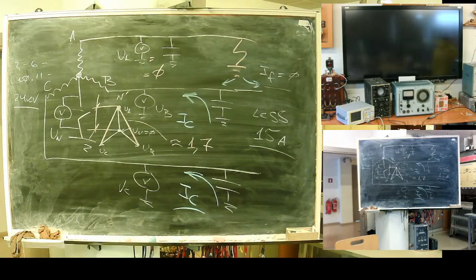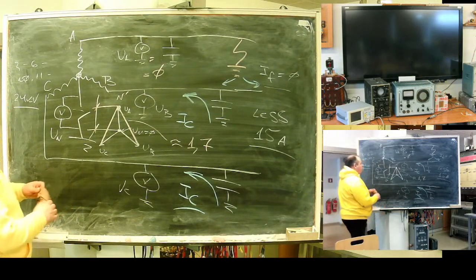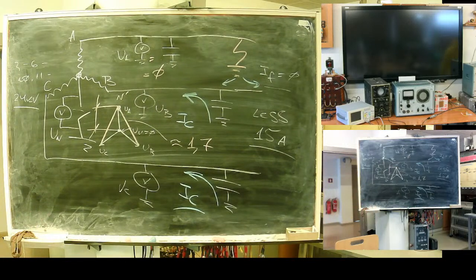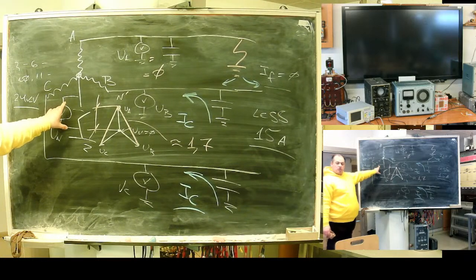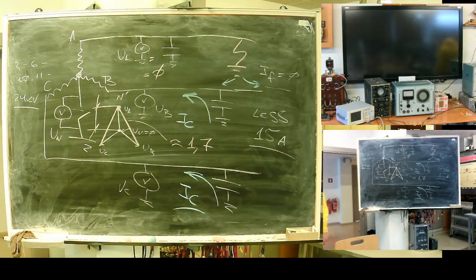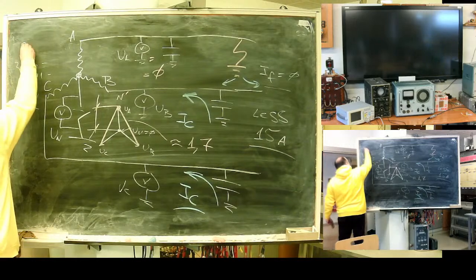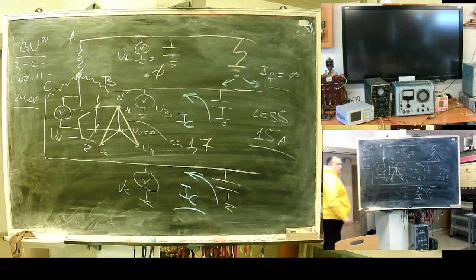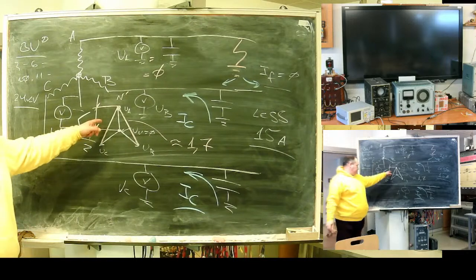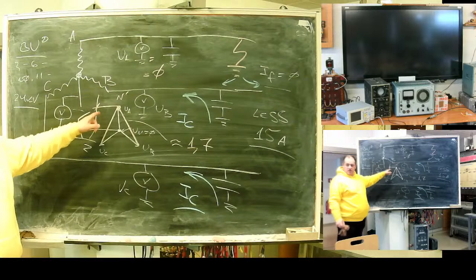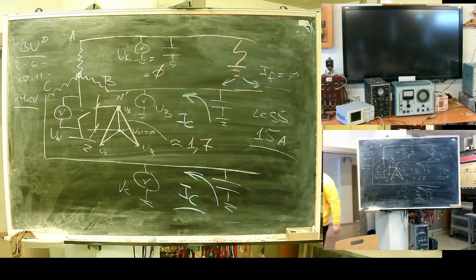Know this. Now, a more complex thing. That's what happens with voltages. Can you measure this voltage? I'm not sure. But you can measure what? Zero sequence voltage, the 3U0. It's a vectorial sum of line-to-ground voltages. You will get 3U0. So you can detect fault presence by the zero sequence voltage.